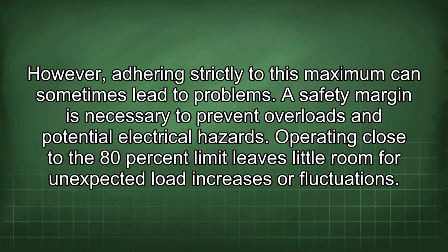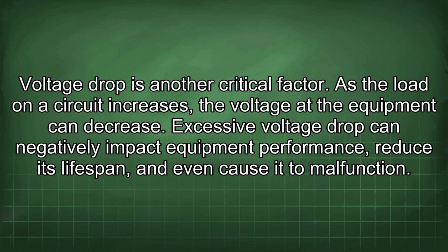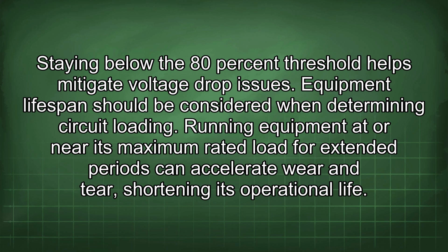A safety margin is necessary to prevent overloads and potential electrical hazards. Operating close to the 80% limit leaves little room for unexpected load increases or fluctuations. Voltage drop is another critical factor. As the load on a circuit increases, the voltage at the equipment can decrease. Excessive voltage drop can negatively impact equipment performance, reduce its lifespan, and even cause it to malfunction. Staying below the 80% threshold helps mitigate voltage drop issues.